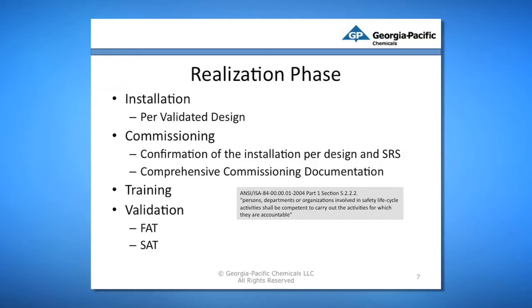We're going to talk about training in a little bit, but talking about validation, it includes validation of I/O, where all the physical and soft connections of all inputs and outputs associated with the SIS are checked, and a functional validation where all programmed logic is checked against the SRS, safety requirement specification.